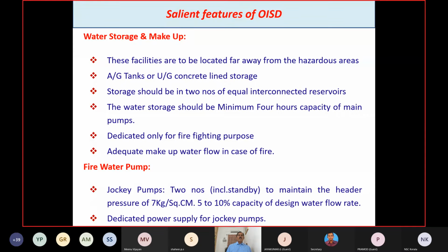So the water storage should be minimum 4 hours capacity of the main fire water pumps, and the water should be dedicated only for firefighting purpose. It should not be used for any other purpose like gardening. And adequate backup water flow in case of fire. In case of any fire situation, we should have an adequate backup water facility. Suppose you have any other raw water storage or cooling tower, we should have a hookup with the fire water system to use it during emergency. And some industries have a hookup with the neighboring company's hydrant lines, because during emergency they can use the neighboring company's water also. This should come through a mutual aid scheme. And fire water pump hose.